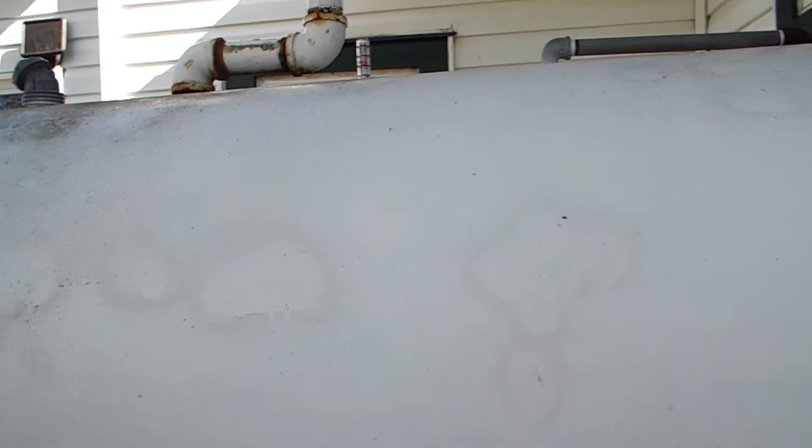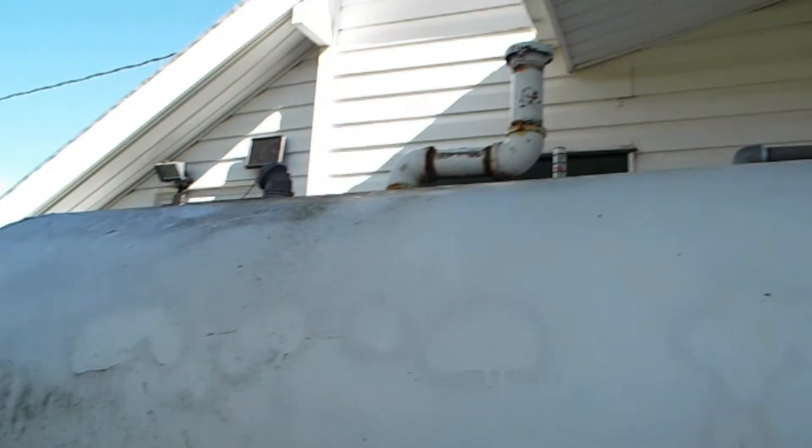There's the vent and the emergency fill. With that tank setup I can take a ladder and use the emergency fill for tank one — the gravity tank — and fill it that way. Or what I normally do is fill tank two from an outside fill, then pump it up to tank one. I can also fill tank three, or fill tank two and open the lower valves to gravity-fill and equalize between tanks two and three so I don't have to pump. With each tank being 275 gallons, when they're all full I can have a year and a half to maybe even two years of heat.